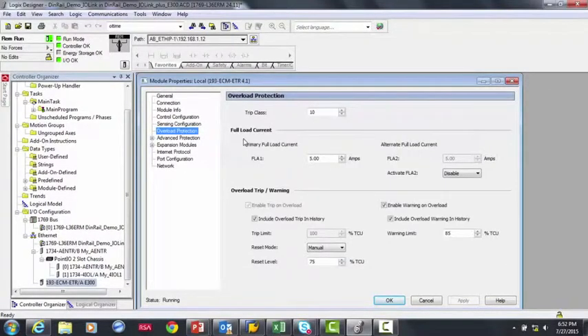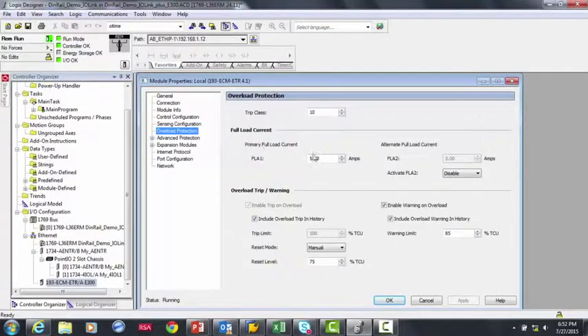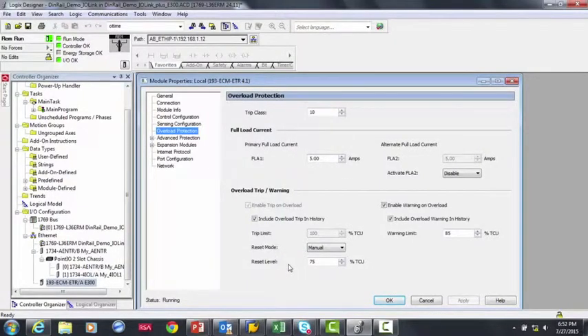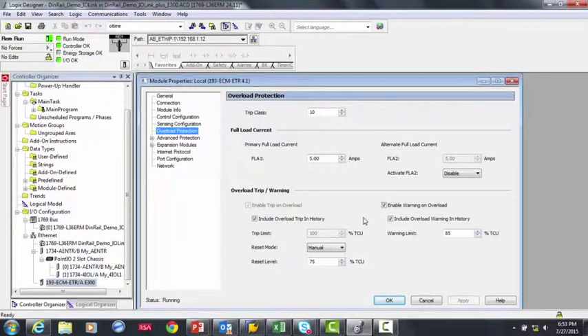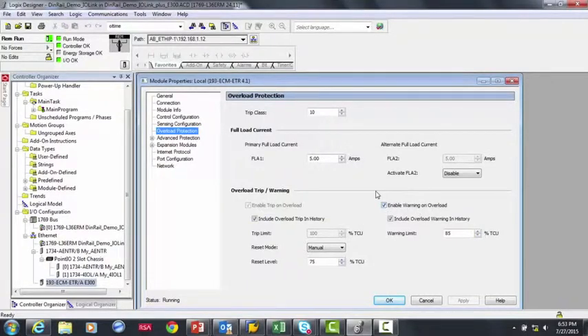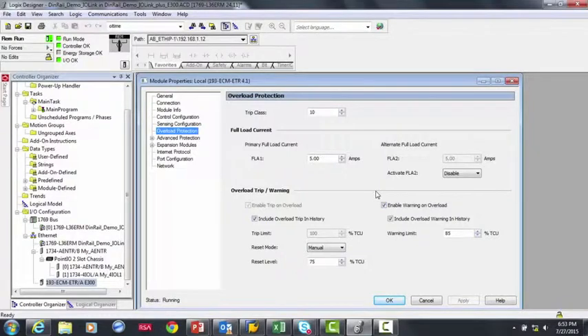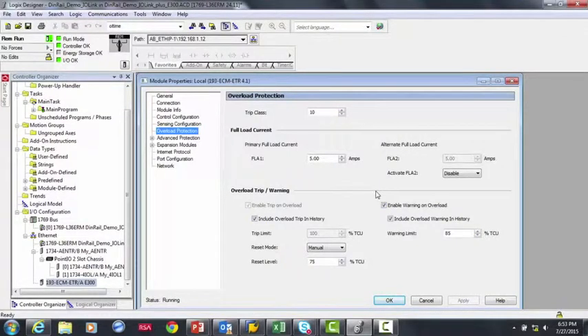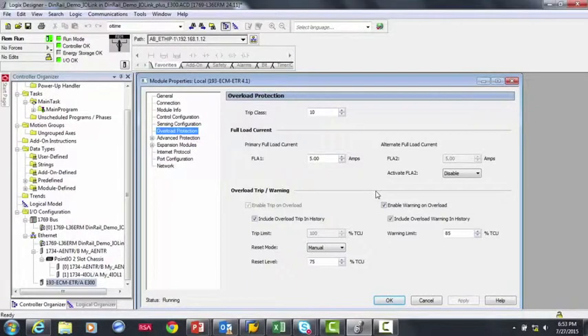If we go to Overload Protection, we can set up the Trip Class, the Full Load Amperage, the Reset Level, so how cool the motor needs to become before it's safe to restart, and we can enable an Overload Warning. The Overload Warning is nice because the E300 can set up an alert when the motor is becoming too hot. This way, you can avoid a trip and prevent downtime.